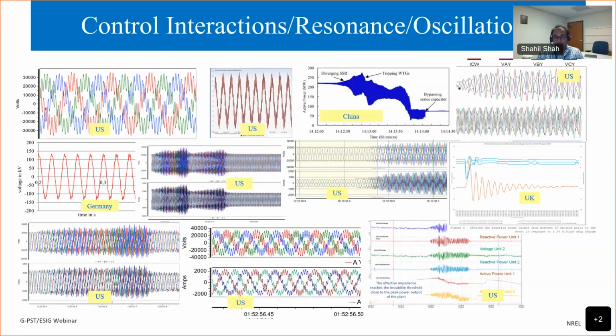So control interactions, oscillations, or resonance have become very common with more and more power electronics that we are seeing in today's grid. They manifest at different frequencies from a fraction of hertz to several kilohertz, and the waveforms that you are seeing on your screen, they are real measurements. So for example, here sometimes these control interactions are sporadic in nature. They come and disappear depending on changing operation conditions and because of change in the damping of oscillation modes.